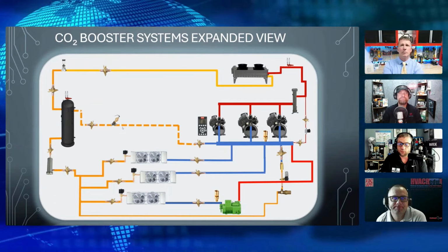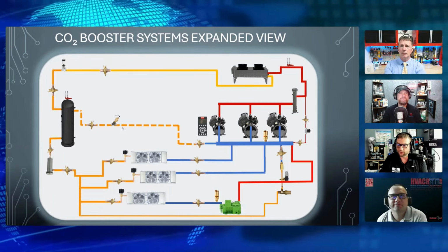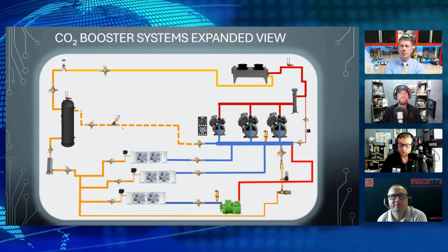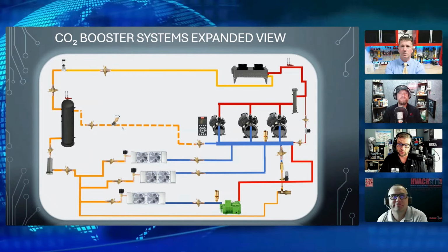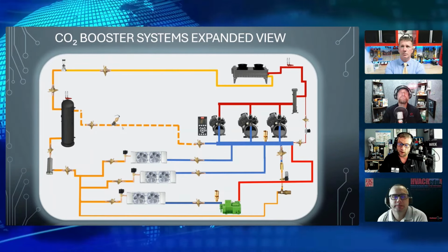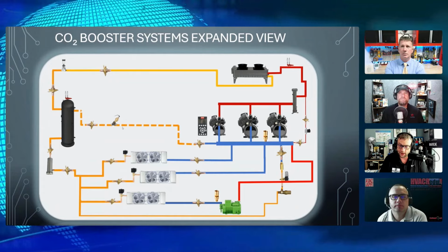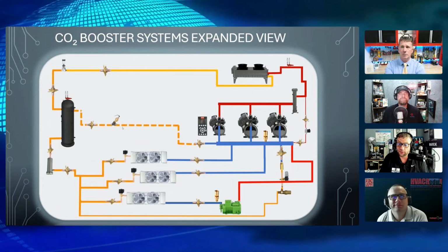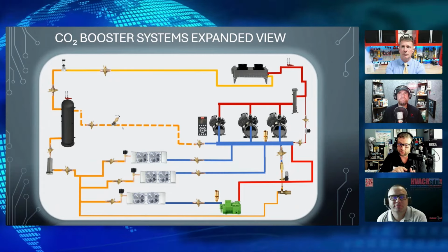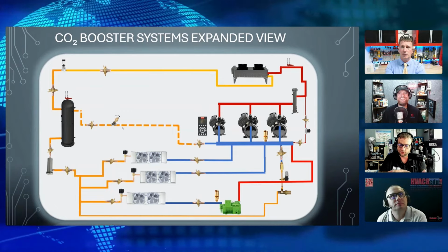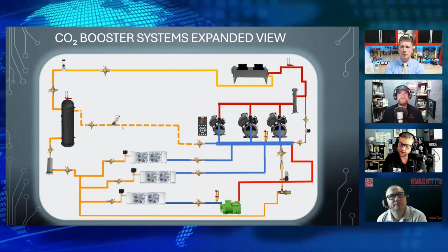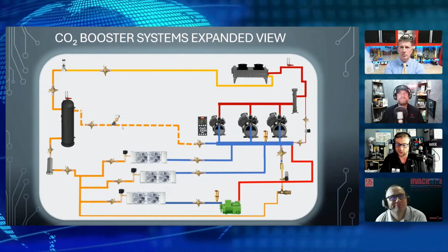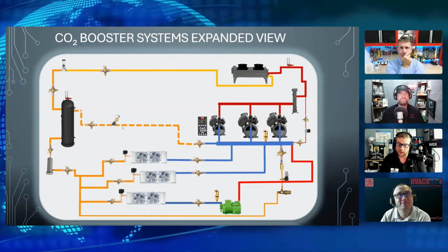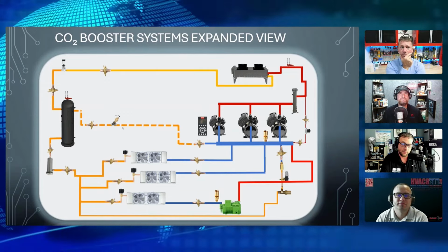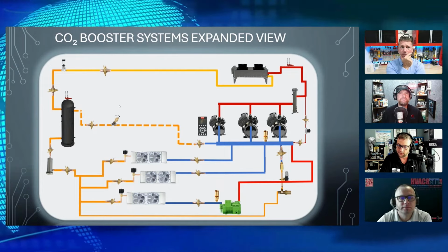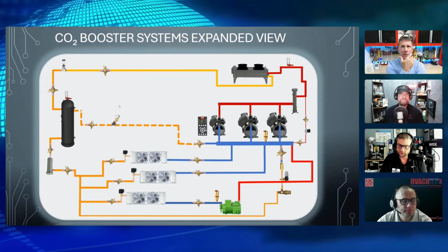A lot of times you'll see maybe four compressors on a system. Two will only run when it's running subcritical, and then when it goes transcritical, those other two will boot up. The reason is that you're creating so much more flash gas that it has to be a consumer of something. If you look at an enthalpy chart, I don't have it on here unfortunately, whenever it makes a little triangle on the left-hand side, that shows wasted energy. Now you have to mitigate that, and that's why you need more compressors. Liquid still goes down through the evaporators, gets run into the medium temp compressors.